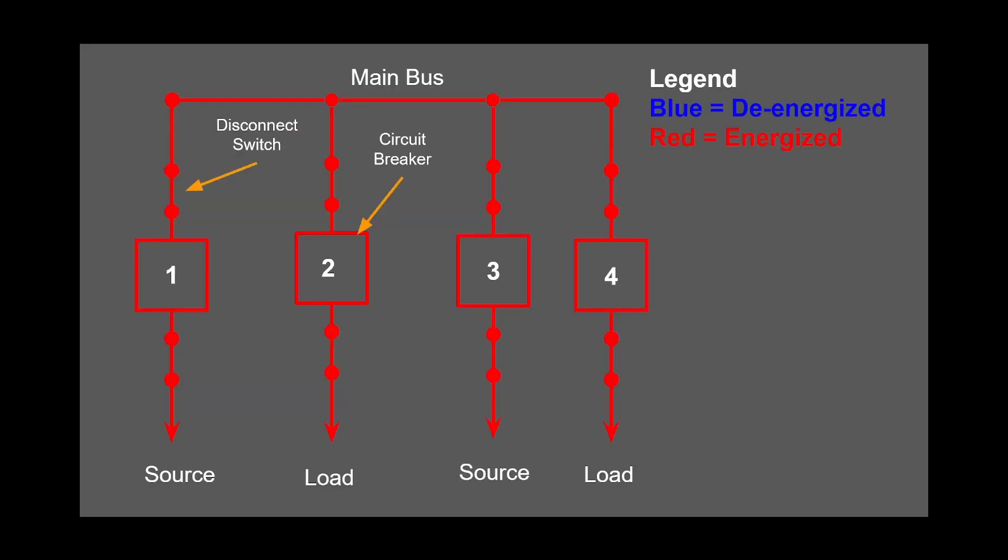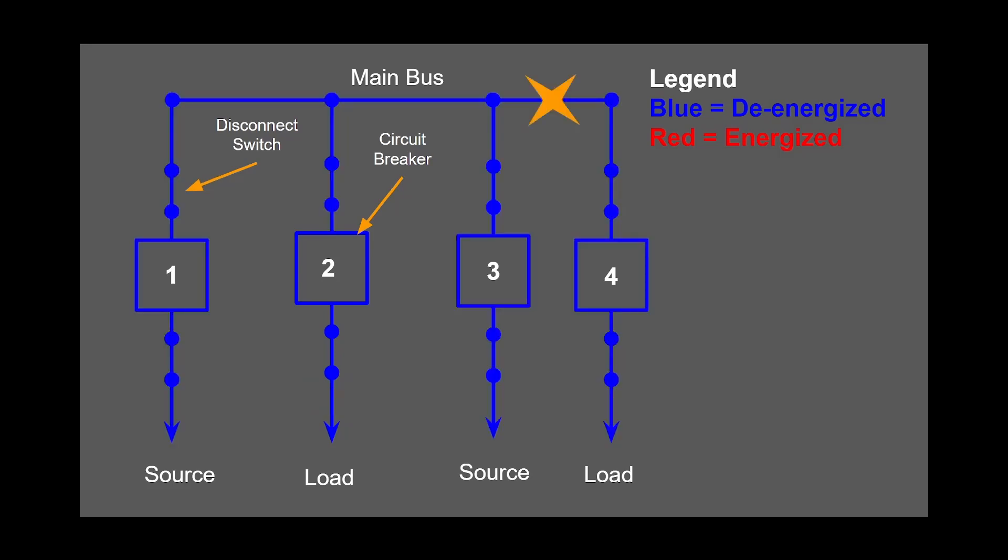Starting off with radial bus configuration. This configuration consists of one main bus, breakers, disconnect switches, and lines that can either be loads or sources. Let's determine the reliability. If we get a fault on the line side of the breaker, then the rest of the system is protected because the breaker will trip. But any customers downstream breaker two will be out of power.